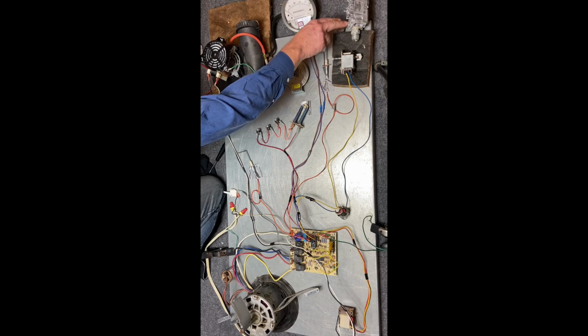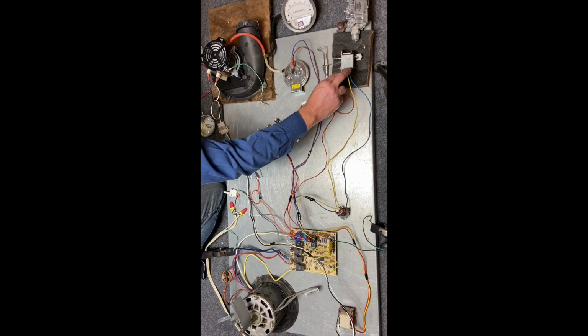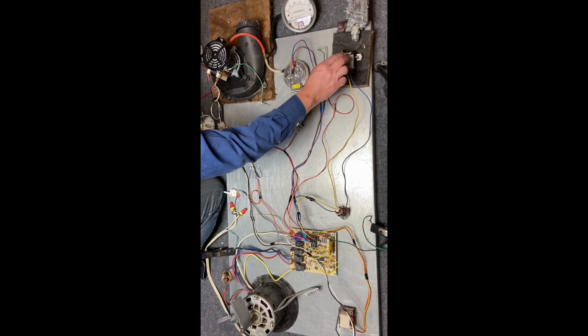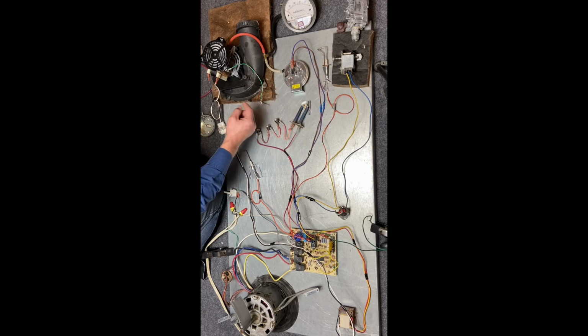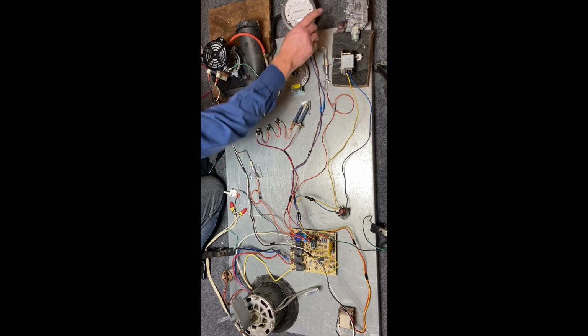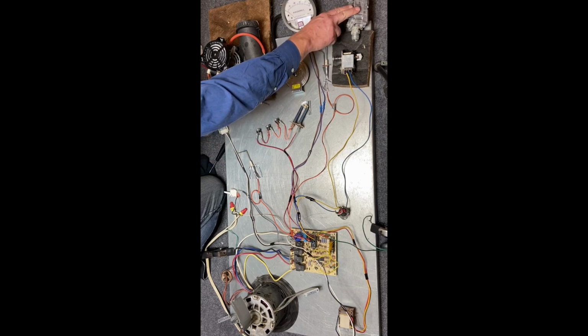So if you have pressure coming in and you don't have any pressure coming out and you have 24 volts here, that means that this is stuck and it's not actually opening. So you have to diagnose this in 2 steps. It's a solenoid valve and also a pressure regulator.